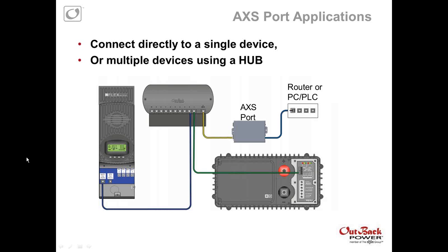Yeah, really, just expanding upon Phil's response there. Really, the only thing that you're limited on is the switching of the stacking. We felt that in order to switch the stacking, someone should be on site and physically see which inverters or which charge controllers are on which line to be able to effectively switch that, because doing that remotely could create some serious problems. But other than that, any functionality that the Mate 3 has in terms of adjusting parameters or functionalities that our inverters or charge controllers allow, you can do with the AXS port.